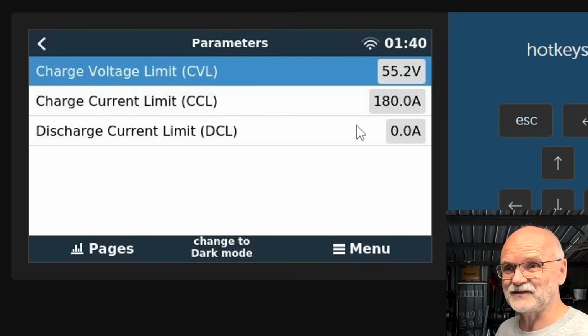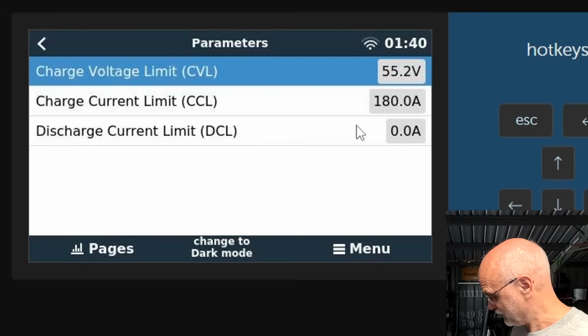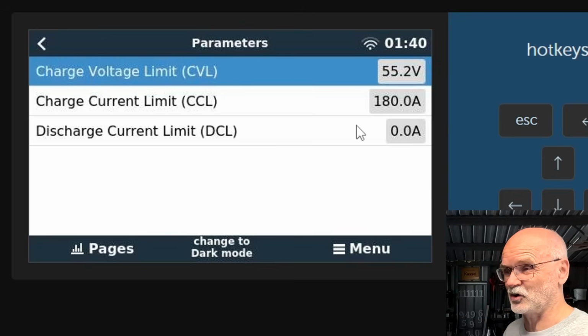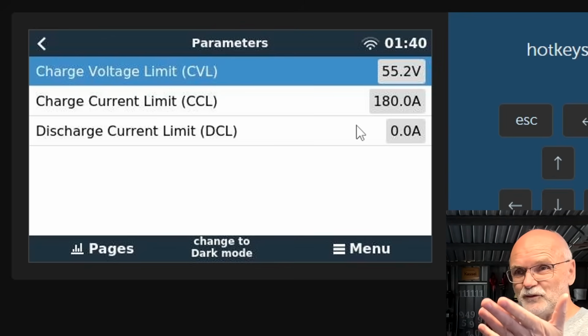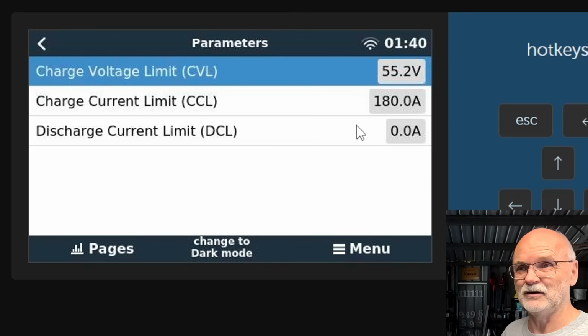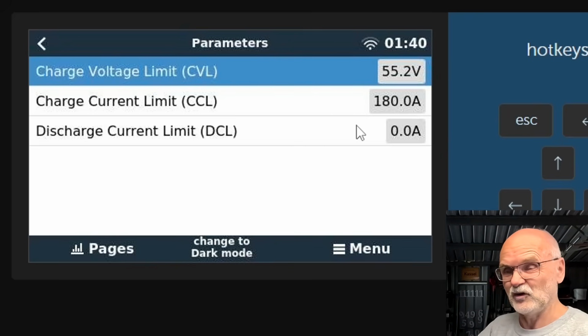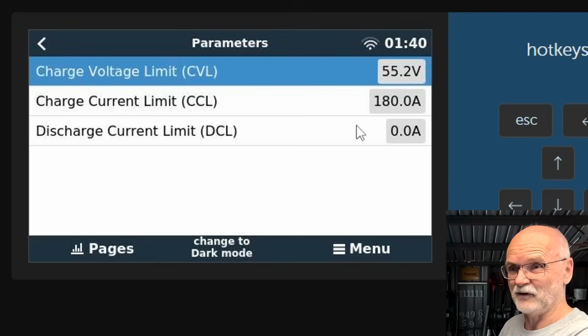Well guys, at this stage I cannot recommend this BMS at all because it doesn't work. It has some serious safety concern issues. See, it should really drop down to 90 amps now. It still reports 2 batteries to your inverter, and the inverter charges full power into only 1 battery now.